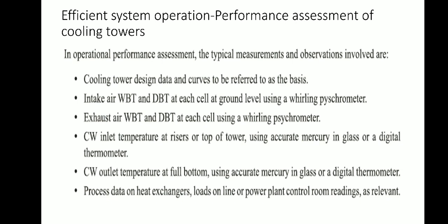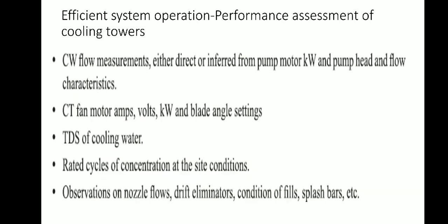Exhaust air WBT and DBT at each cell using a whirling psychrometer. Cooling water inlet temperature at risers or top of tower using an accurate mercury in glass or a digital thermometer. Cooling water outlet temperature at the basin using an accurate mercury in glass or a digital thermometer. Process data on heat exchanger loads in online or power plant control room reading as relevant.